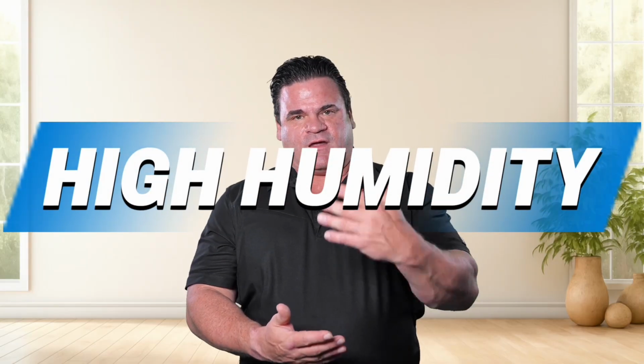So while it's still cooling, latent heat is the humidity in the air. The capacity that it's putting out is closer to that of a 4-ton. So if your home needs a 5-ton, and now this is derated down because of the temperatures to a 4-ton, what's the natural and probable outcome? It's going to take longer to cool your home. So high humidity, another big issue.